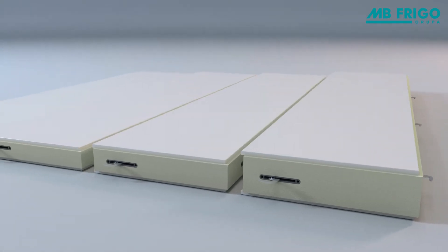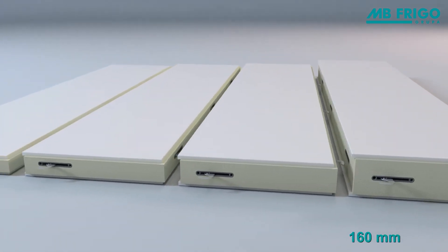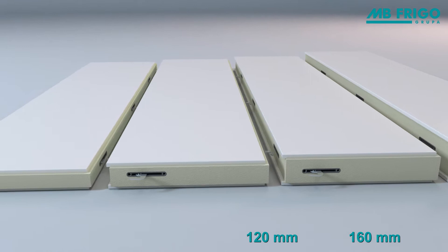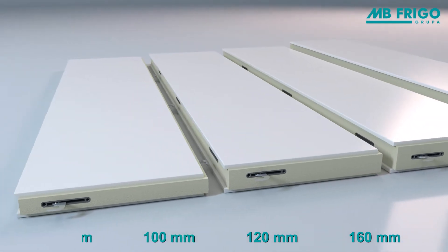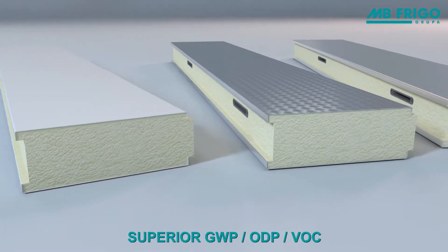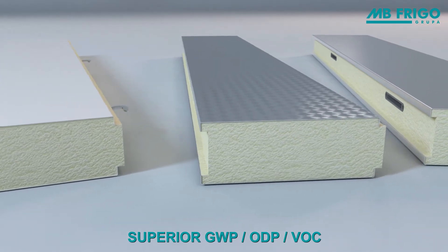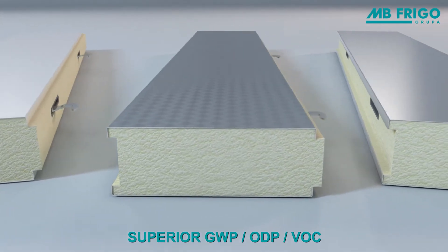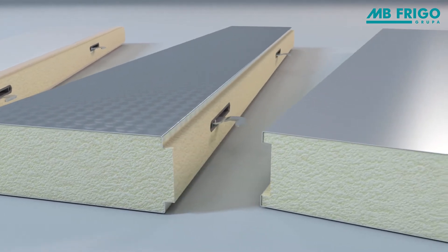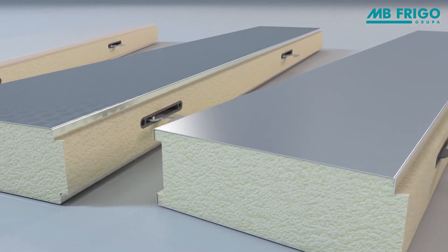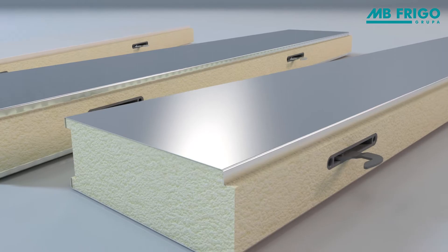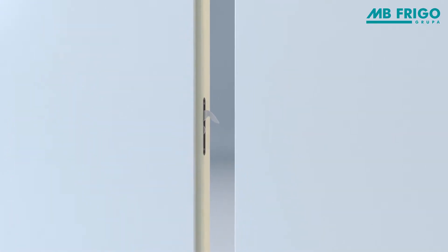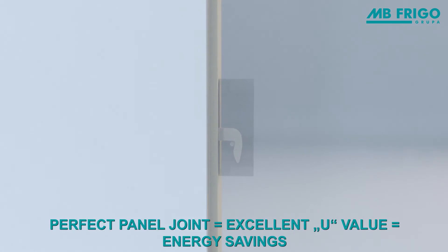We make panels with the following thicknesses: 160, 120, 100, and 80 millimeters. Our panels are filled with HFO foam, which has excellent heat insulation properties and conforms to the regulation on certain fluorinated greenhouse gases. Automated production and precise panel connections prevent air infiltration from outside and into the cold room, and thus contribute to achieving the energy efficiency standards prescribed by the eco-design directive.